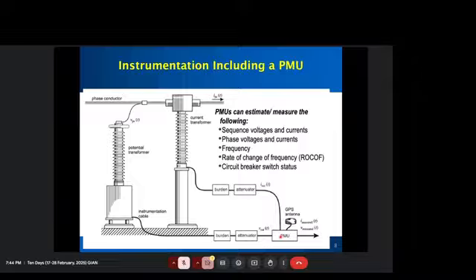Then you apply a certain burden and attenuator, and give it to the PMU, which needs analog input from voltage, and also analog input from current. This is a current transformer, which means it has to be connected in series with the high voltage conductors, so it can measure the current. Then similarly, you get the low voltage with a very high ratio, like 1000 to 1 or 500 to 1, with a burden attenuator, and feed it to the PMUs.